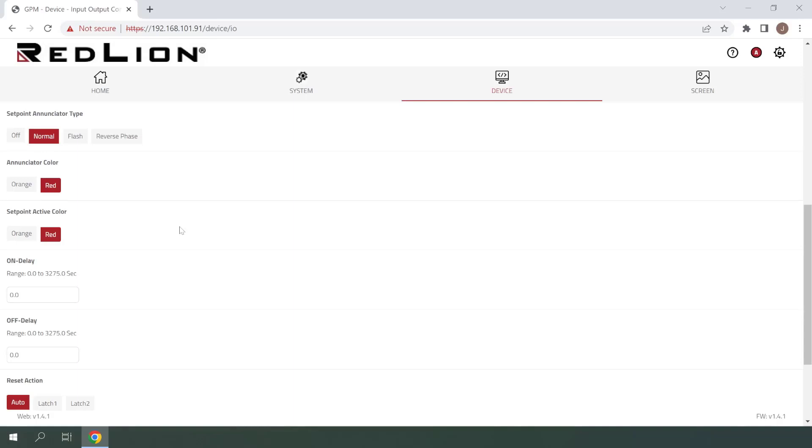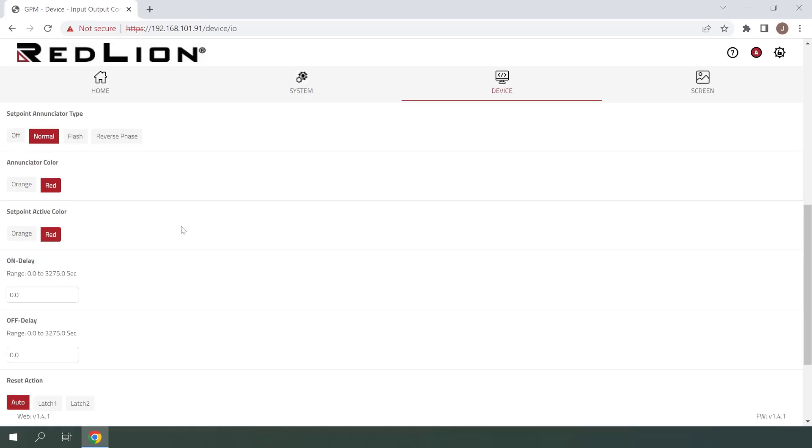Next up, we see Annunciator Color and Setpoint Active Color. The annunciator color refers to the color of the banner which appears around the edge of the screen when the setpoint alarm is active. Setpoint Active Color is the color used in the Setpoint Status widget and icons to show the active state of the configured setpoints individually. One thing to note here is that red has precedence over orange for both of these color settings.